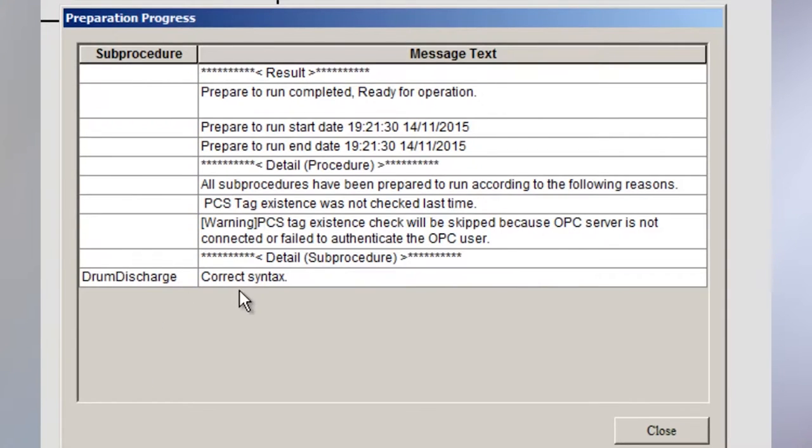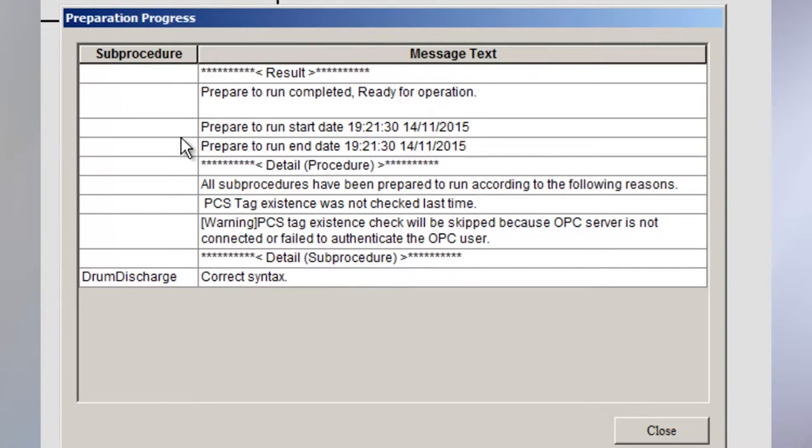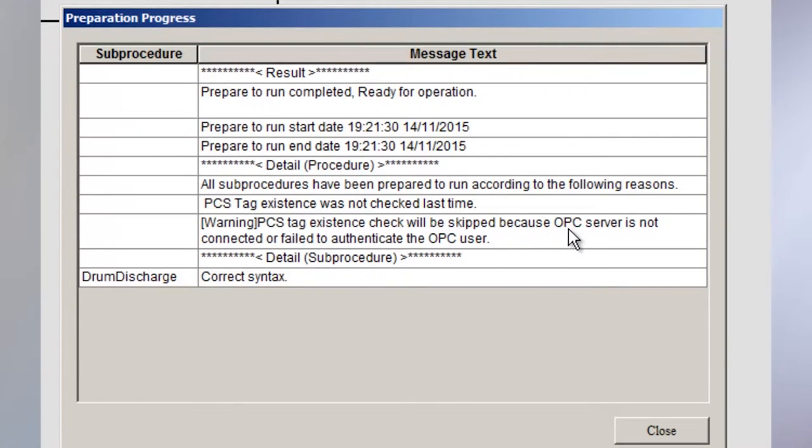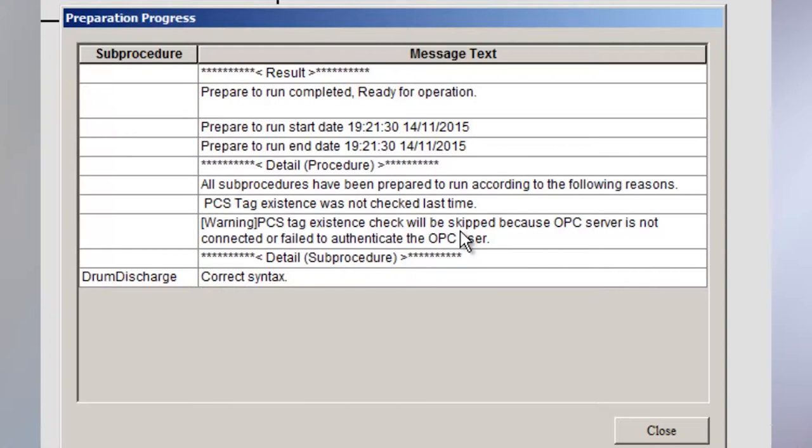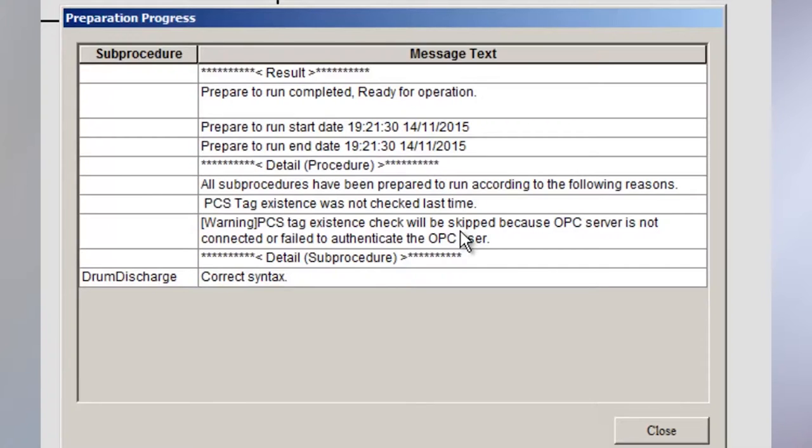And if everything goes well, we'll get a correct syntax at the end, which I did here. I just want to point out we do have a warning. And the warning says, PCS tag existence check will be skipped because OPC server is not connected or failed to authenticate the OPC server. That's a normal message you'll get when you're in offline mode or standalone mode. I'm not connected to an OPC server or OPC server simulator. And I'm not connected to a real system. But we can still test the procedure if it compiles with correct syntax.